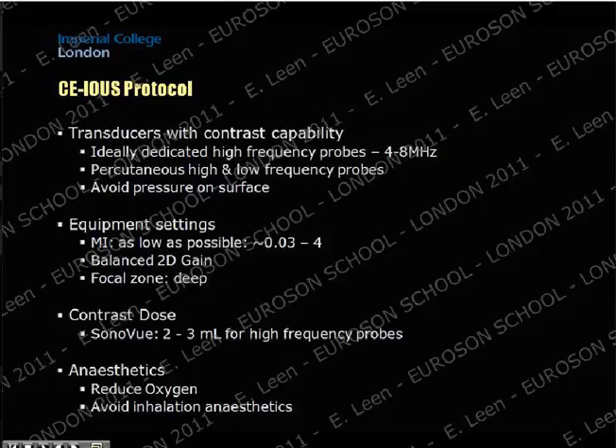And again, what I'm going to go through is some of the limitations of the percutaneous probe itself. But I think the first thing is the application of pressure. There's a tendency of us putting a lot of pressure on the probe when we're scanning. But intraoperatively, you shouldn't do that, because especially with microbubbles, you destroy a lot of bubbles on the surface in the first place. And not to mention the fact that the compression compresses the capillaries and the whole thing.